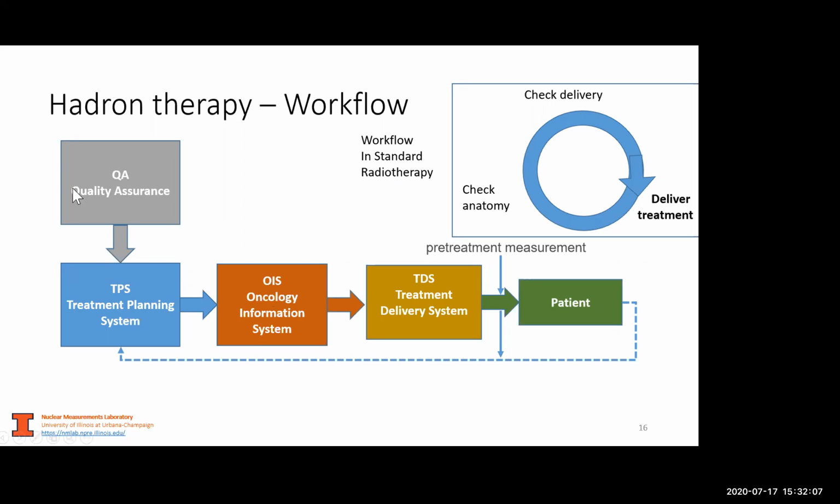The treatment planning is done upon performing quality assurance on the machine, which is typically a process that takes approximately 30 minutes and is done daily. And it is very critical to make sure that the delivered dose is what it is set to be.